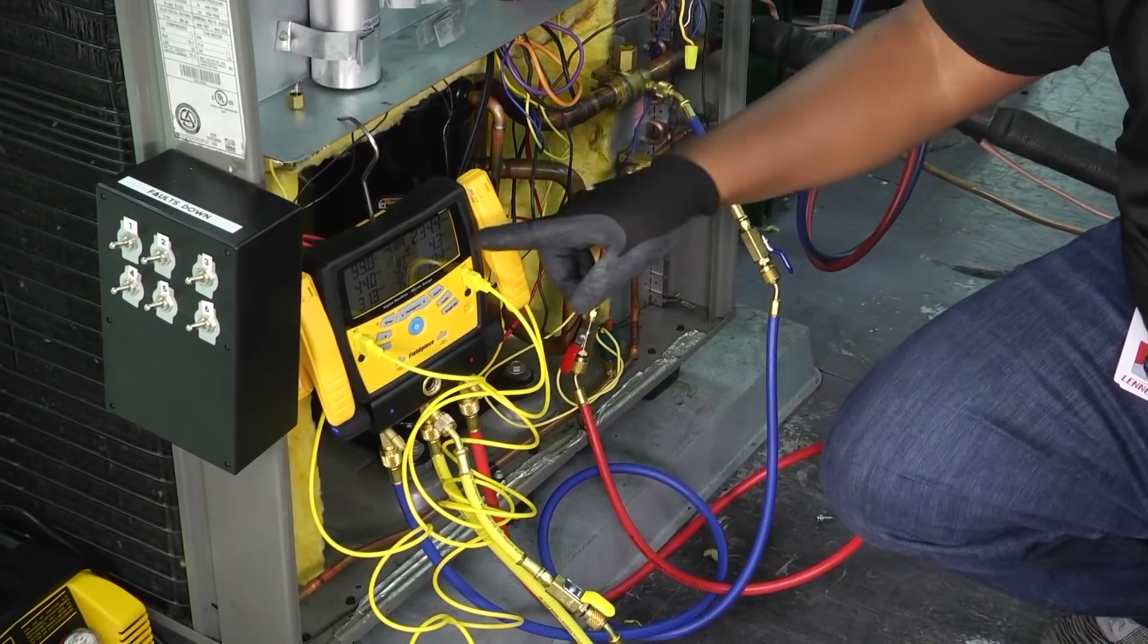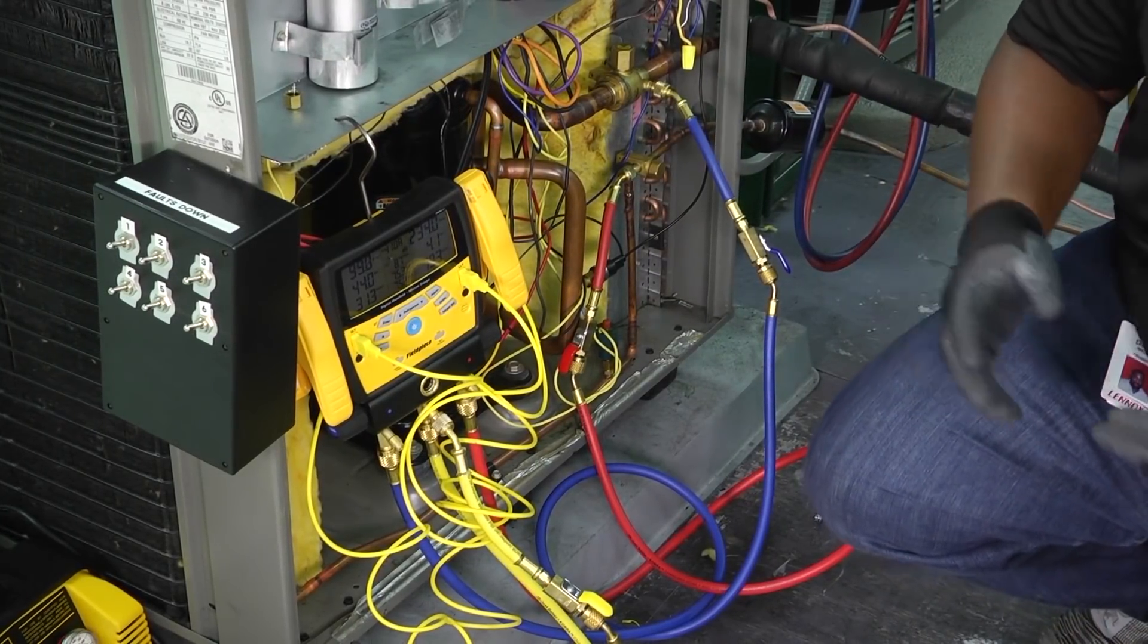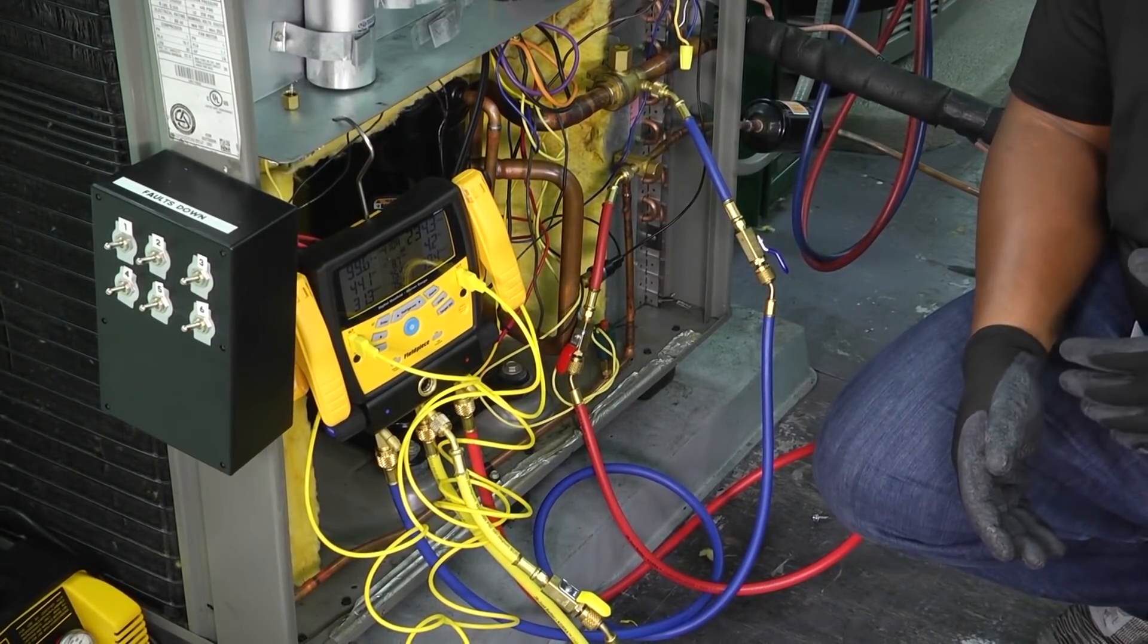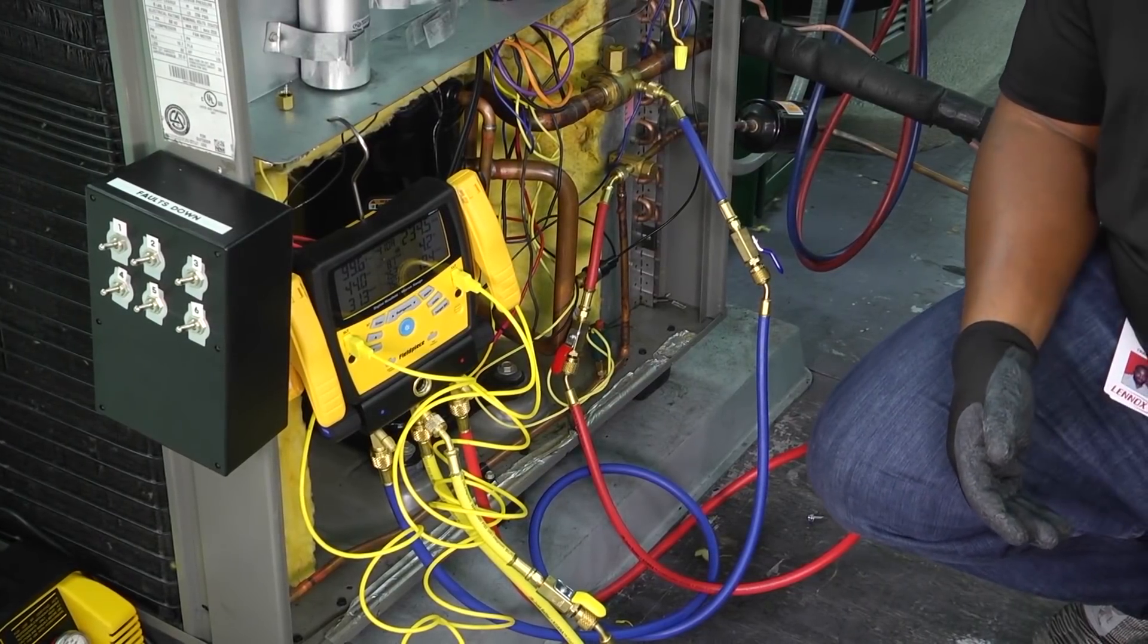If we have a TXV, then we're going to charge by the subcooling number. Subcooling is really easy. If the subcooling is too high, then we take refrigerant away. If the subcooling is too low, then we add refrigerant to our system.